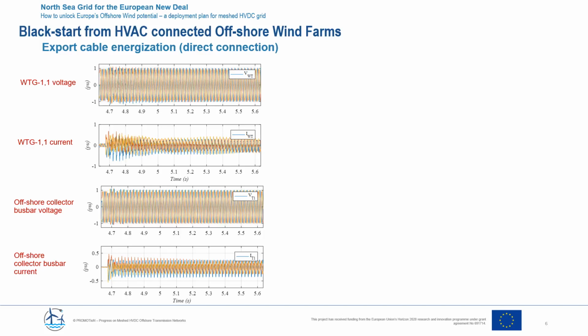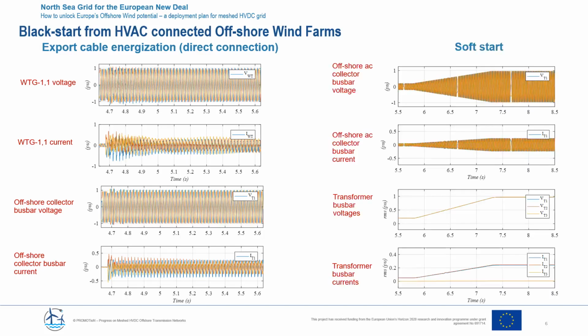The alternative, you can see it on the right, where we perform the soft start, where all the wind turbines are synchronized with a relatively low voltage. All the switches down to the onshore grid are closed, and then the voltage of all the wind turbines is ramped up. That can be done relatively quickly, as we don't have this kind of resonances, and obviously we avoid over voltages and over currents.